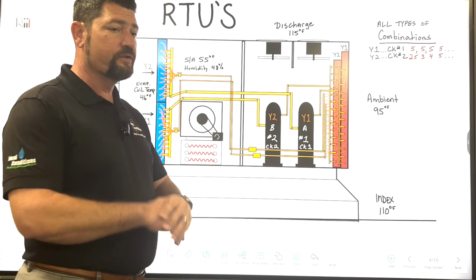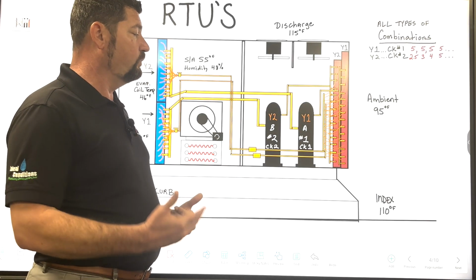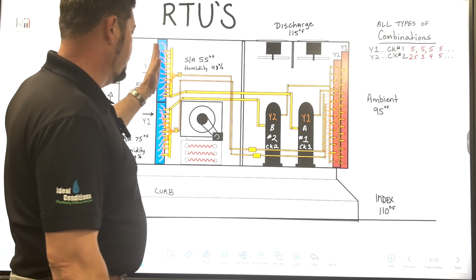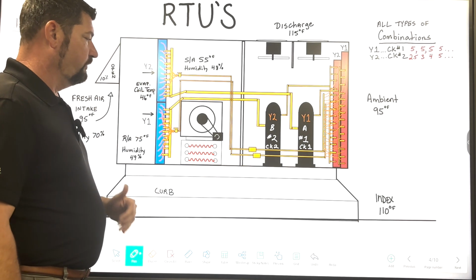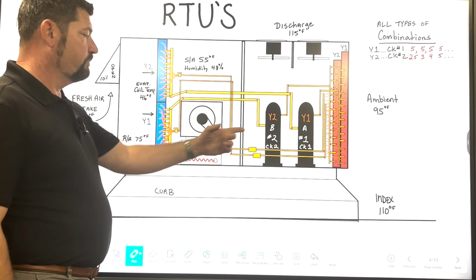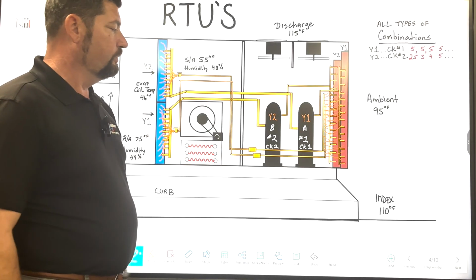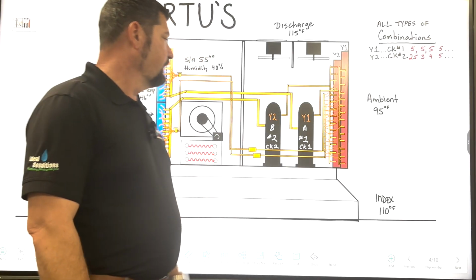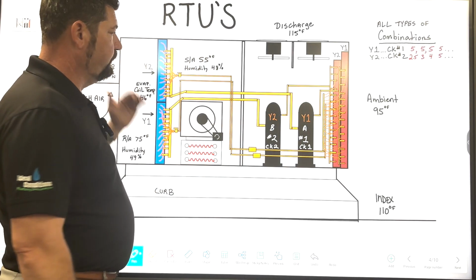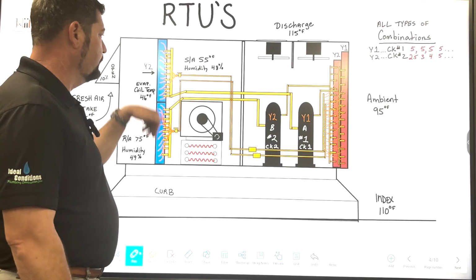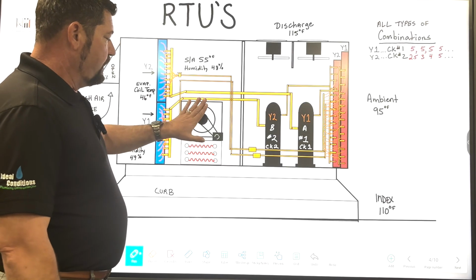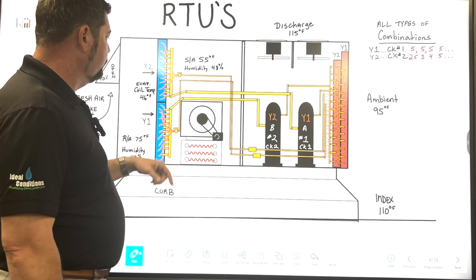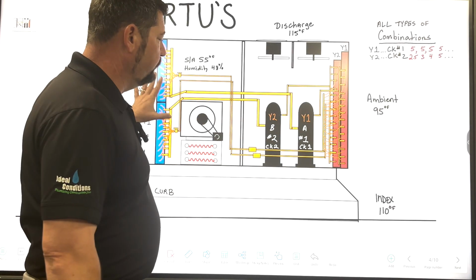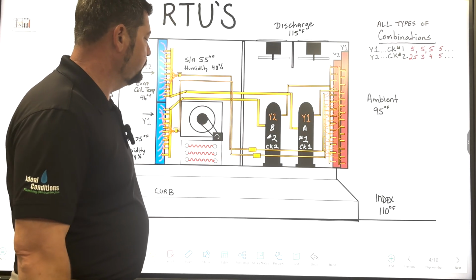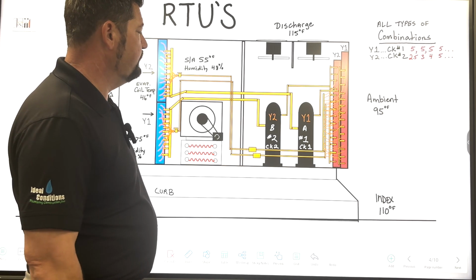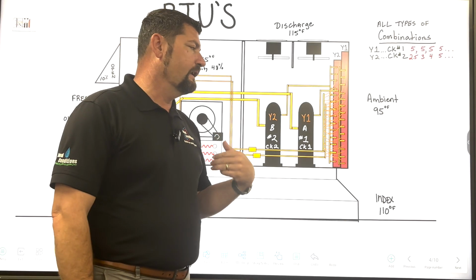And sometimes it's just a sticker, and those stickers can come off, and you may not know which one is which. The easiest way to tell is your evaporator coil. If the bottom section of the coil is cold when one compressor is running, then that compressor would be circuit 1, right? And so you want to make sure that sequence is correct so you're not adding that humidity back into the building that's being pulled out. Same thing, we got our blower, we have our belts, heat strips. Looking at our refrigerant circuit, it's just a straight cool. I did not really feel like putting a heat pump up here. That'd be a little bit more piping, and I think I would only busy this up and confuse you.